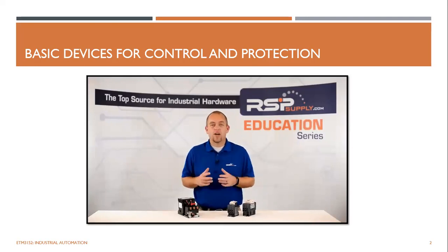A magnetic contactor is operated electromechanically without any need for intervention. This allows us to operate the contactor remotely, so we don't have to put any kind of operators in any sort of dangerous situation that might be close to our motor starter. So in order to function properly, a contactor uses a small control current to open and close the contactor. Most contactors typically have auxiliary contacts as well. These contacts allow us to monitor the state of the contactor, whether the motor is actually on or off. Some contactors have multiple auxiliary contacts to monitor other types of systems in the contactor.